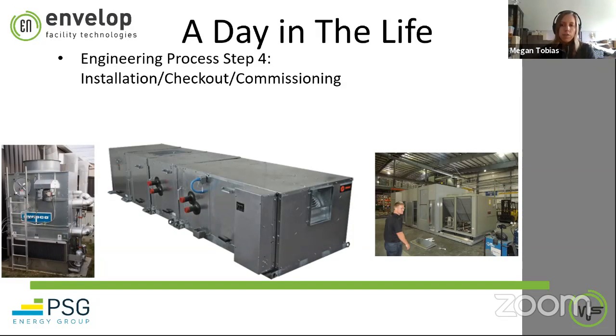Then we have field technicians who go out and do what we call a point check on the system to ensure everything's working properly. For example, I told this fan to run—did it actually come on? Am I seeing status feedback? We do that for each individual system, from room level all the way up to the big air handling units, which there's a picture of here in the middle as an example of an air handler. On the left, that's a cooling tower.